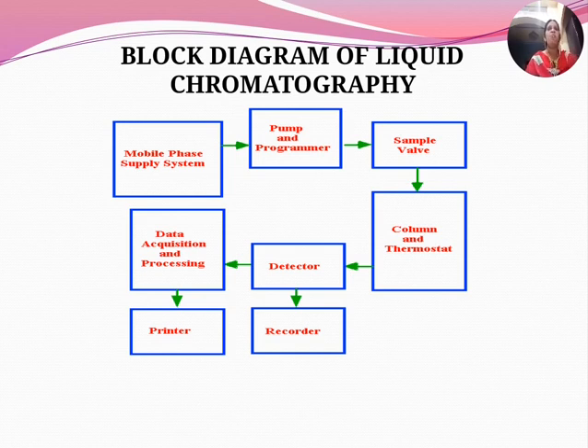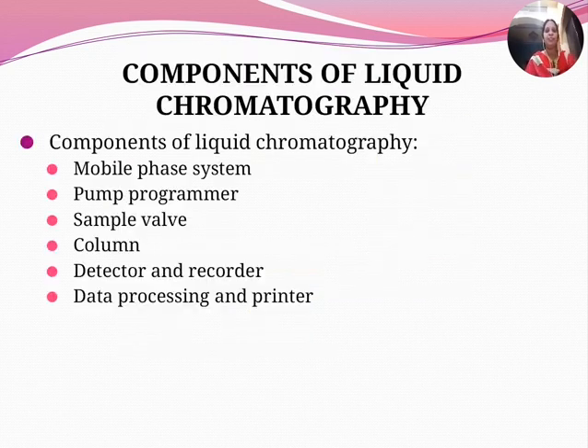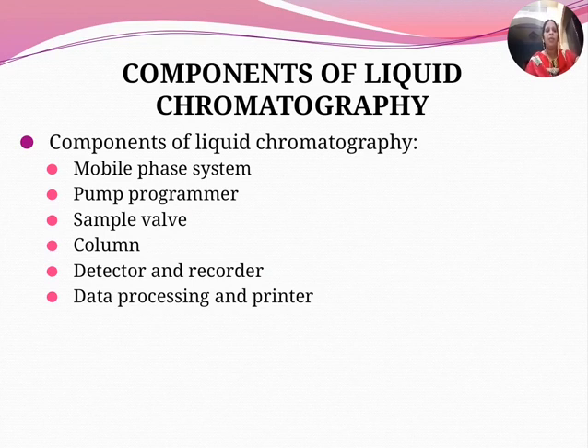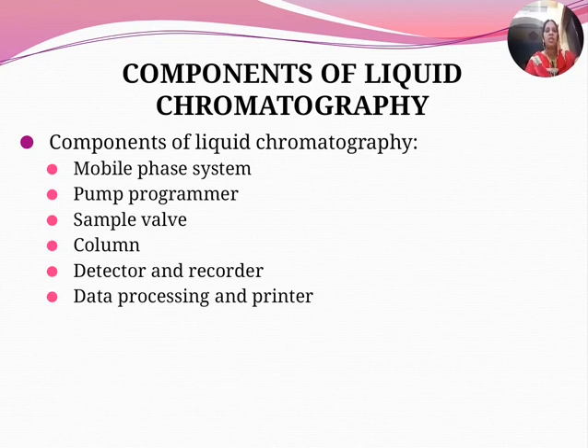The components of liquid chromatography are: the mobile phase system, the pump and programmer, the sample valve, the column with thermostatic control, the detector and recorder, and data processing and printer.